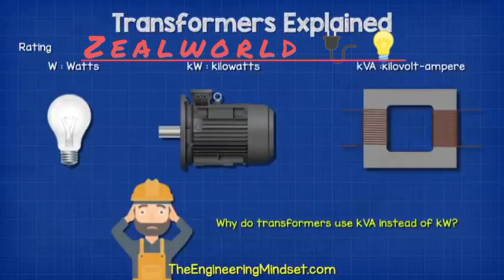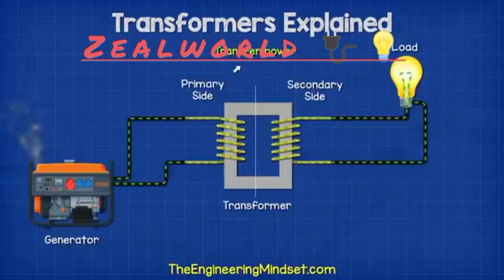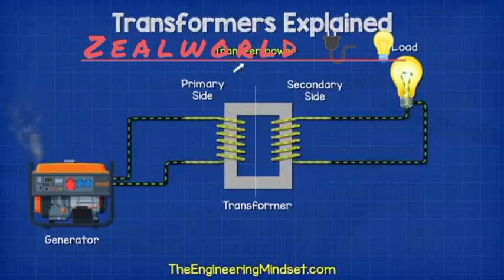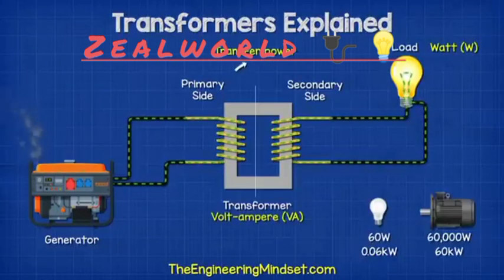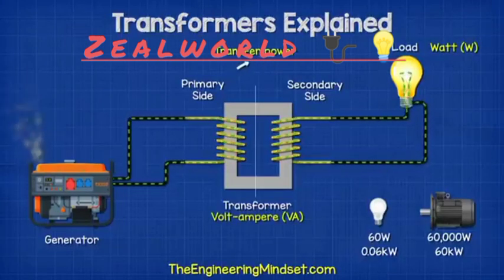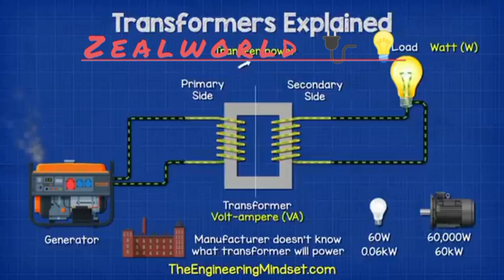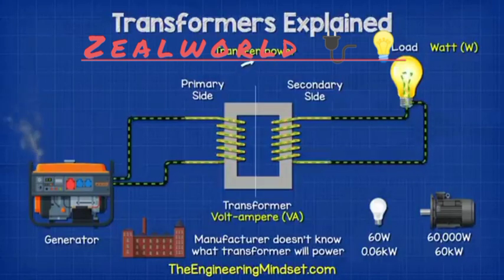So why do transformers use the units of kVA instead of kilowatts? Well, the transformer is just transferring power between the coils, so we use the volt amp unit. The kilowatts depend on what you connect to the transformer. The manufacturer doesn't know what you will connect to the transformer, so they state the total rated apparent power in volt amps.